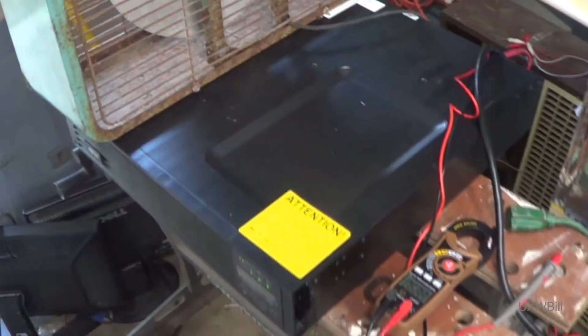Now that we've returned to the proper line frequency, I'm sure you've noticed how smoothly and quietly this fan ran. That's because this uninterruptible power supply's inverter has a true sine wave output characteristic. I'm not sure where my scope meter is, so you'll have to trust me that because of this thing's role as a high-end power protection device, its output waveform is in all probability better than even the best utility power out there. That's its job -- it's got to protect the equipment to which it's attached.